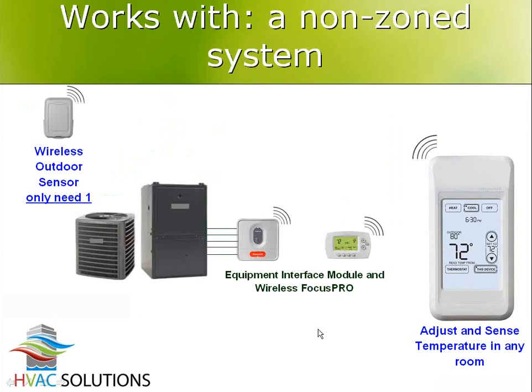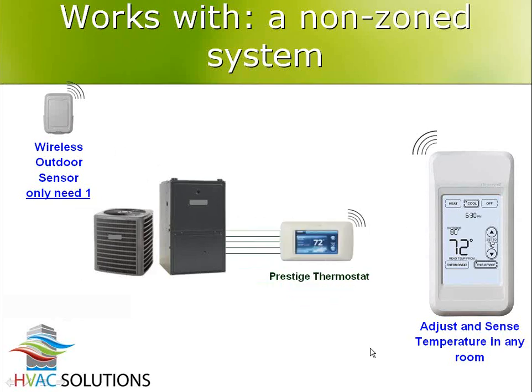Okay, so this is what a system might look like. This is using a non-zoned FocusPRO wireless stat. He is talking wirelessly to the equipment interface module. That module is hardwired to the furnace or the air handler. He's physically sitting next to it there in the basement. And then I could have my portable comfort control talking wirelessly to my stat, and I can have my outside air temperature talking wirelessly to the stat. So the stat is kind of the focal point. He's talking to the equipment module, he's talking to the portable comfort control if I'm using one, and he's talking to the outside air temperature sensor, all three of the devices.